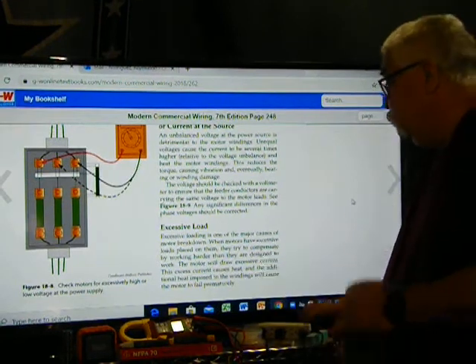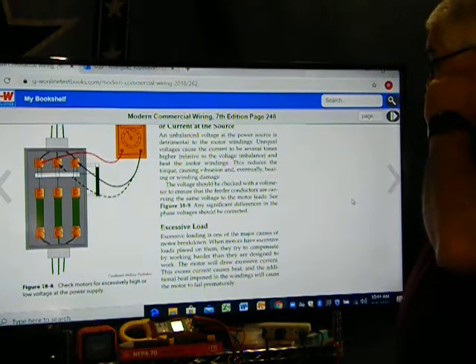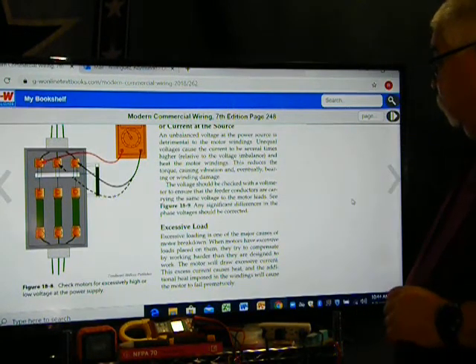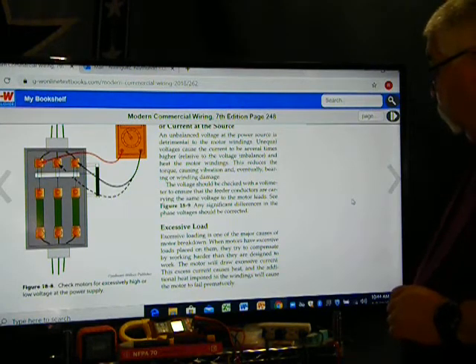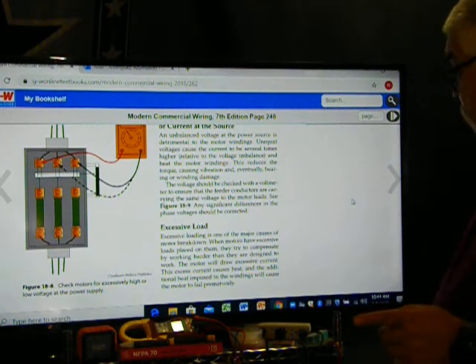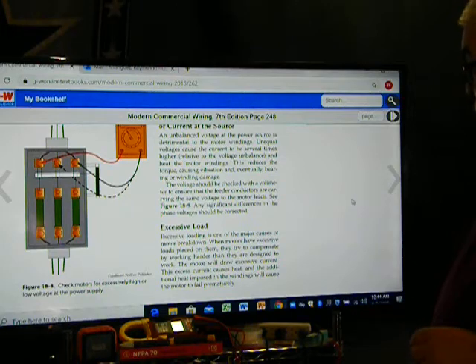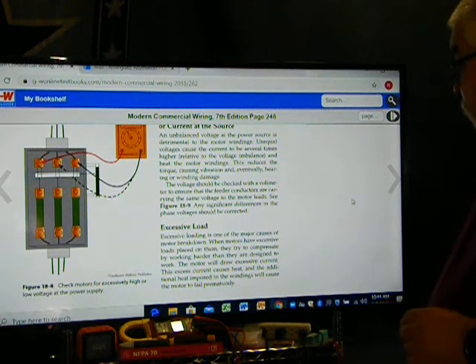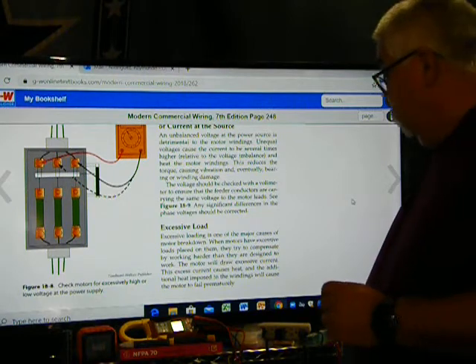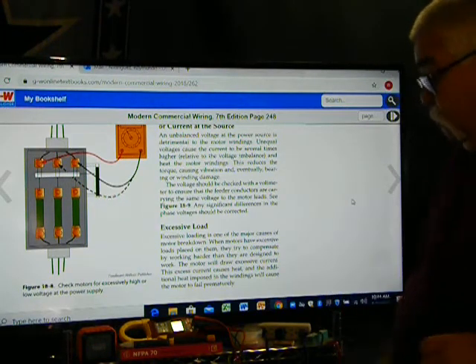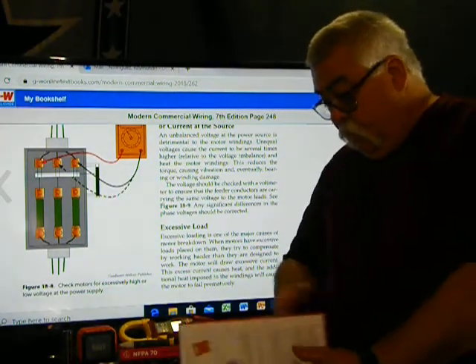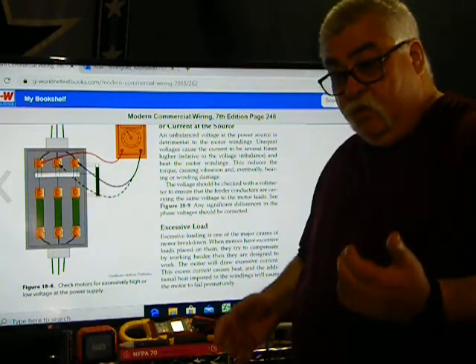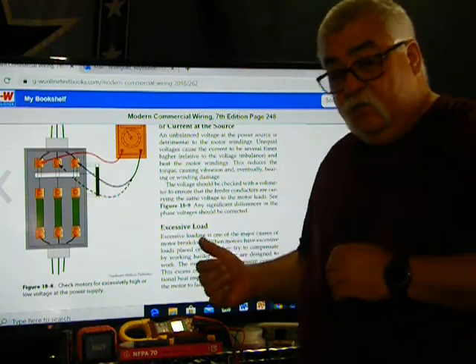Down here it says excessive load is one of the major causes of motor breakdown. When the motors have an excessive load placed on them, they try to compensate by working harder than they are designed to. The motor will draw excessive current. This excessive current causes heat, and additional heat imposed on the windings can cause the motor to fail prematurely. So you have to be careful with excessive loads.